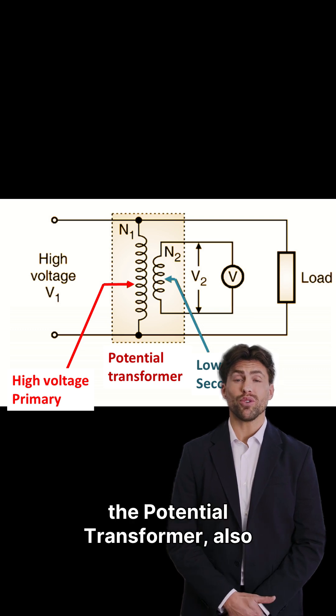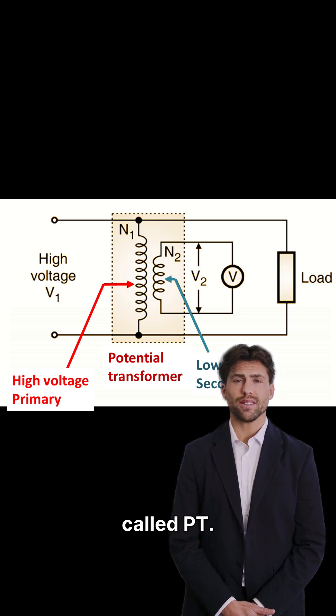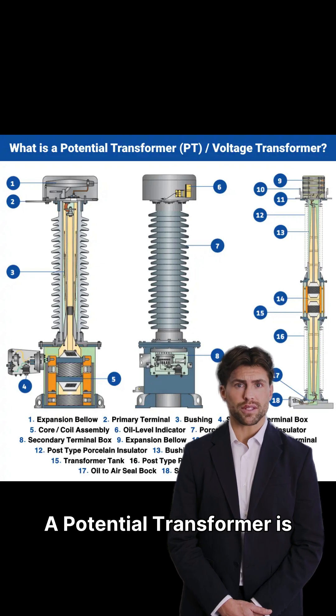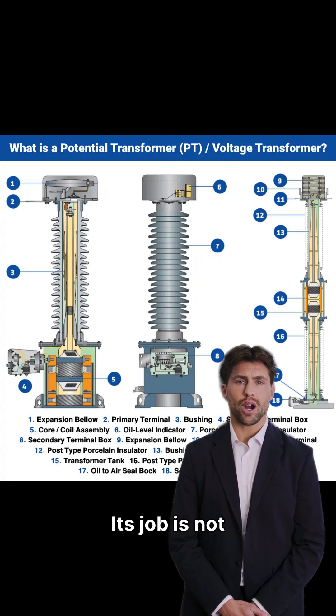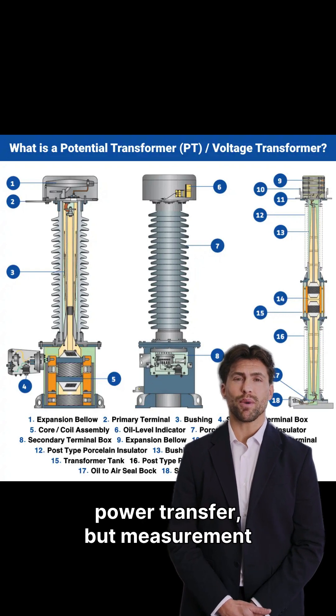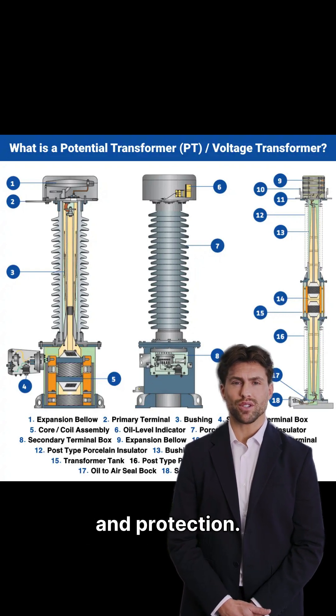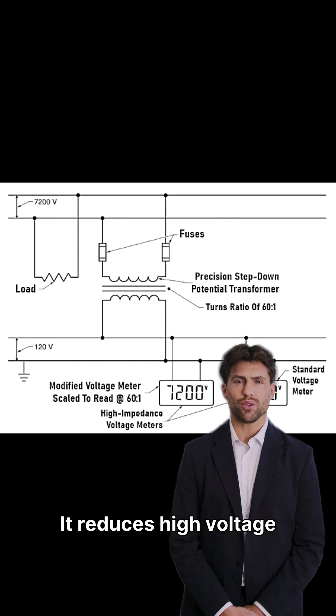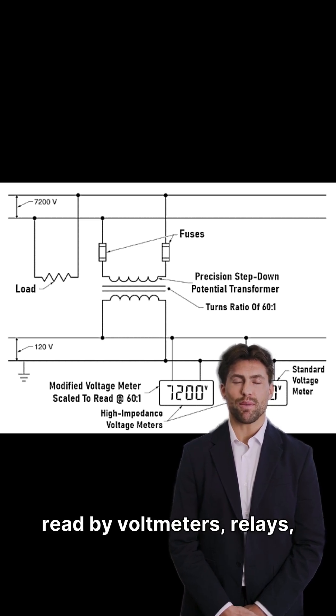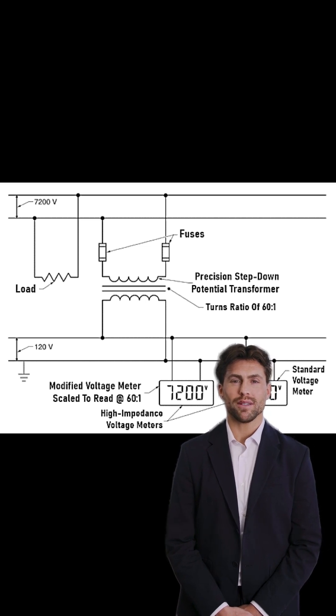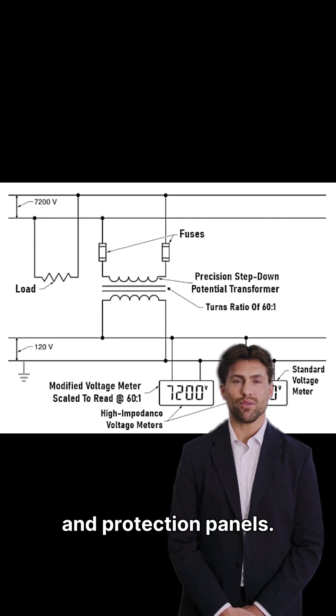Now let's talk about the potential transformer, also called PT. A potential transformer is a special type of voltage transformer. Its job is not power transfer, but measurement and protection. It reduces high voltage into a safe, exact value that can be read by voltmeters, relays, and protection panels.